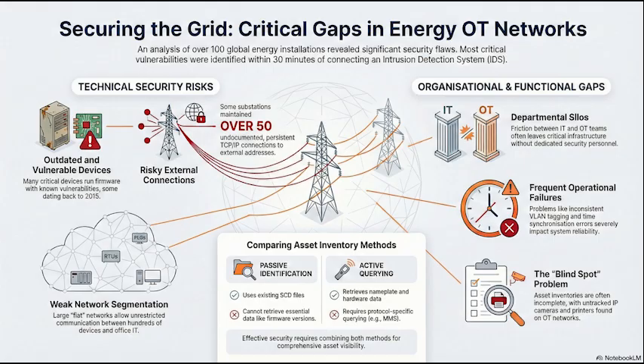So if I'm a relay and I see a fault, I send a GOOSE message to the breaker saying open up. Exactly, and that message has to arrive in milliseconds. The study found inconsistent tagging of these messages. If the network switches aren't configured right, that GOOSE message gets stuck in traffic.